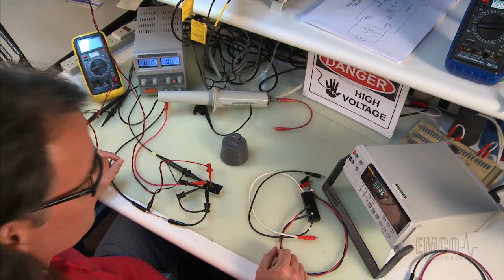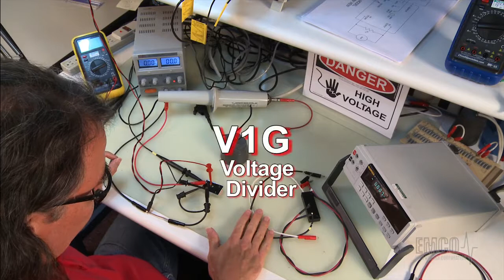Again, in this case, I'll use two methods to measure the output. I'll use the DMM here with our V1G voltage divider to get a very accurate measurement, and then we'll also use a high voltage oscilloscope probe to measure the voltage on the oscilloscope. First of all, the V1G is a 1000 to 1 voltage divider that is compensated in order to match the 10 megaohm impedance of the DMM. So we can connect that to the DMM and connect the return lead to the high voltage return this time, and then we need to connect the high voltage output. I'll use a high voltage standoff here to make that connection, and I want to make sure we connect the high voltage lead such that it can't short to the case, because of course the case is at high voltage ground.